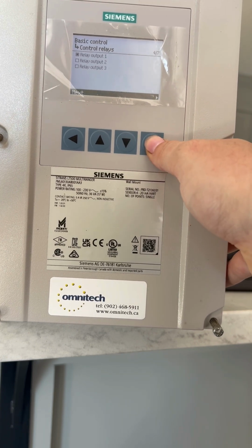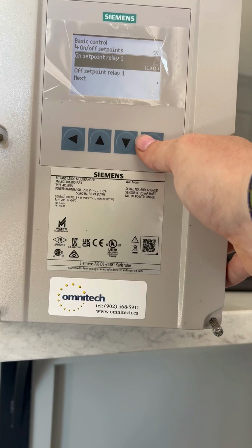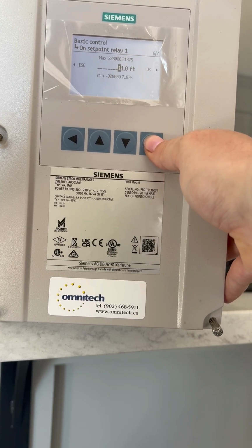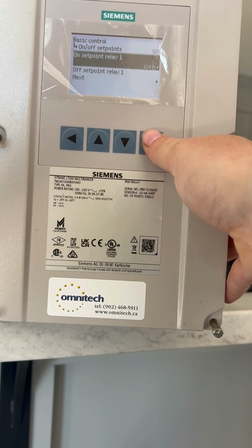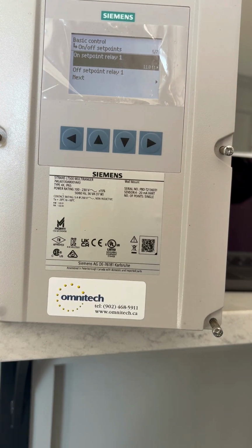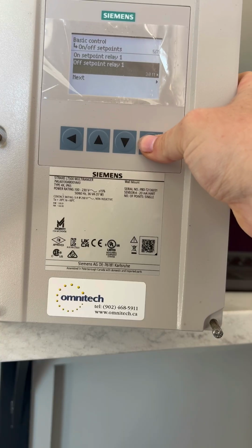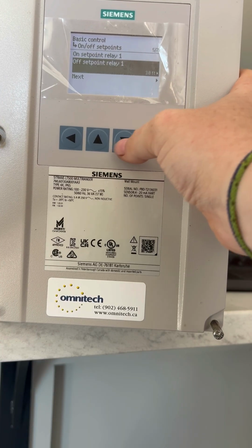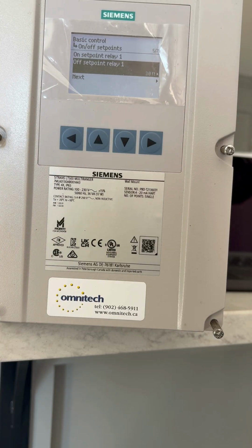I could go into a different one if you wanted to wire up differently. And then I have my on set point as 11 feet. If you wanted to change it, again, you just go into here. So like I mentioned, once this is installed, say we're only at 11.5 feet and then you want the relay to actually activate at 10.5 feet, then you just go in here and make that change. And then the off setpoint, at this point I have on at 3 feet, just so that if there is an issue and something doesn't work, it won't just keep trying to turn it on. If you want, you can change that. You could have that down to 0. Again, I just picked a number really. It gave you quite a wide range. So when it's between 11 and 12 feet, it does not have that relay activated. When it's between 11 and 3 feet, it does have that relay activated.